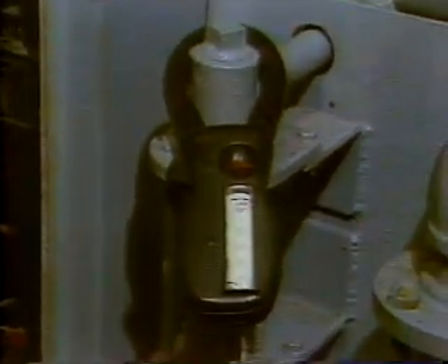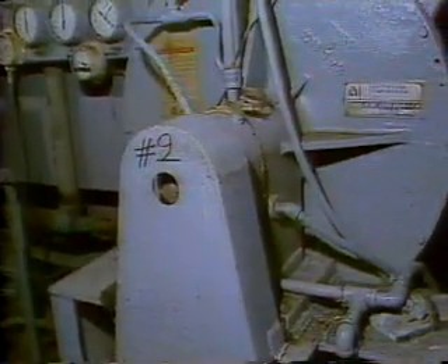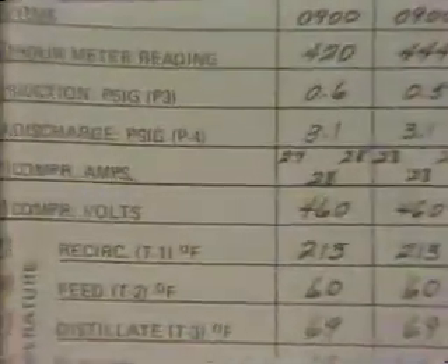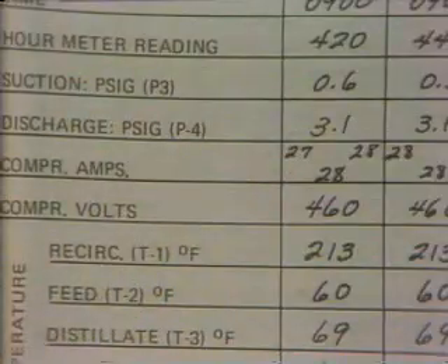To check the amperage, the electrician will use a clip-on ammeter, like this one. It should be read only after the compressor has had a chance to get up to operating speed. All three phases should read within 10% of each other. Again, the proper specs can be found in your maintenance manual. These readings are entered on the logs here.